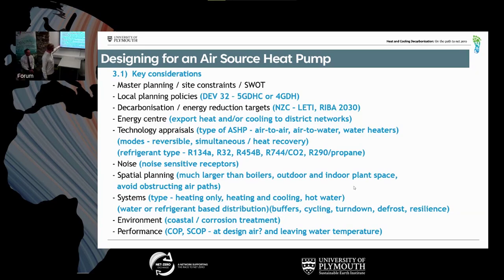Won't go into too much detail because this is a lot of refrigerant numbers, but there are natural refrigerants that are coming out. They've been around for a little while. Some of them are CO2. Sounds strange, but actually you can use it as a refrigerant and it's got a global warming potential of 1. So it's very good in terms of the environment, although I'm trying to save CO2. Seems strange that we want to put it into a heat pump and use it as a refrigerant, but actually it's because of the charge and the volume is very minimal. So at the end of life, when you release that, it's really not that bad for the environment.